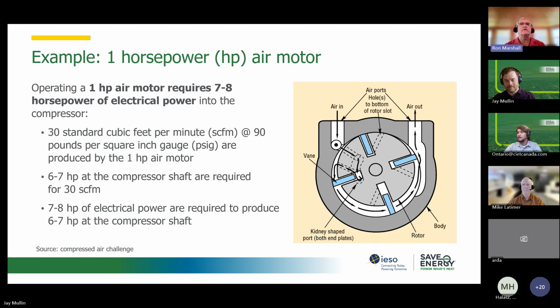Very good. Thank you. Yeah, so the course basically said, and this is a course from the Compressed Air Challenge, Fundamentals it's called, that to produce a 1 horsepower output at the shaft of an air motor like this, that's showing us a vane motor, it needs about 30 standard cubic feet at 90 pounds. At the compressor element inside the compressor, six or 7 horsepower is required to turn that shaft. And then there's an electric motor, of course, between the input electricity and the shaft. 7 to 8 horsepower of power is required at the compressor to produce 1 horsepower at this device.